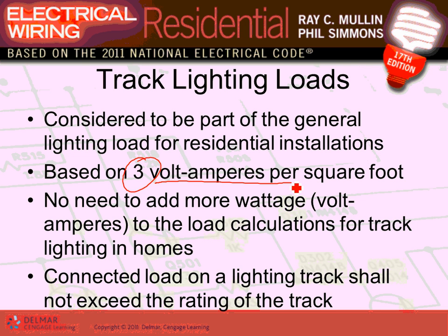You do not add. Here's what it does say: lighting track shall not. Can you guys see the word "not" here? You do not add any extra load for track lights when you're doing dwellings. So for track lights, no extra load added. Show windows, we give 200 volt-amps for show windows and track lights and so forth.